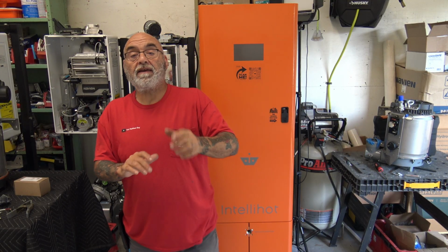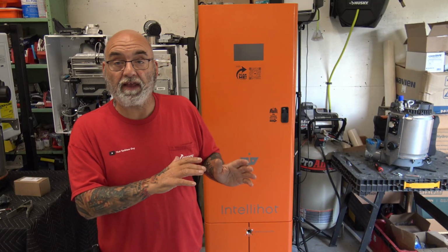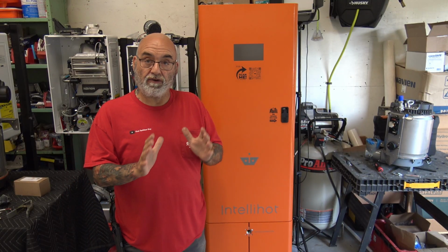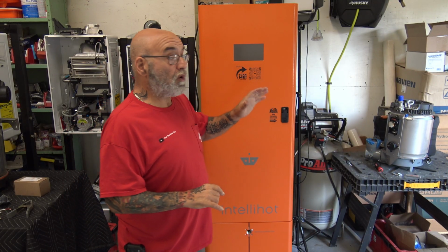Today we're going to start troubleshooting and repairing IntelliHot units, and we're going to go with the water flow sensor valve. Basically that's the water turbine that detects the water coming in, spins up a turbine, which then sends that information to the PC board, which then ramps the burner up and down.